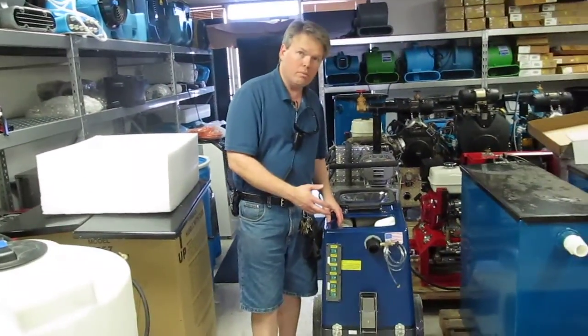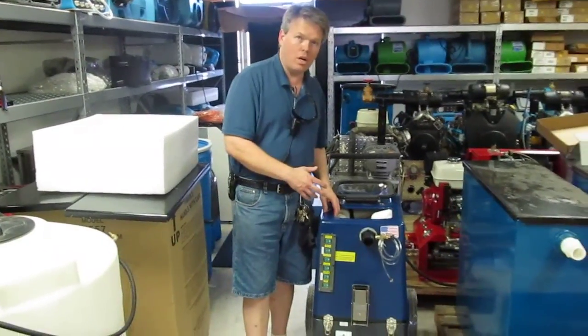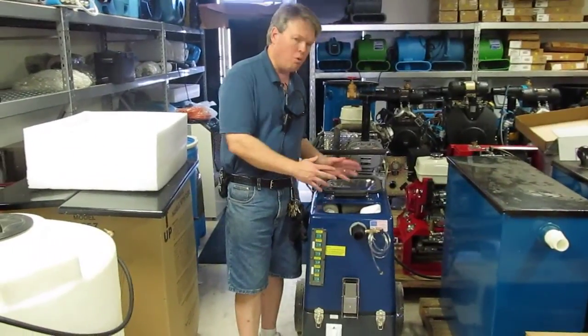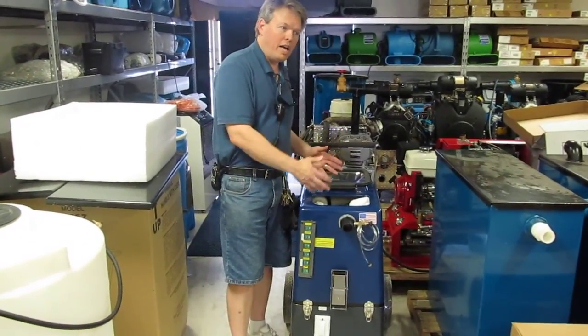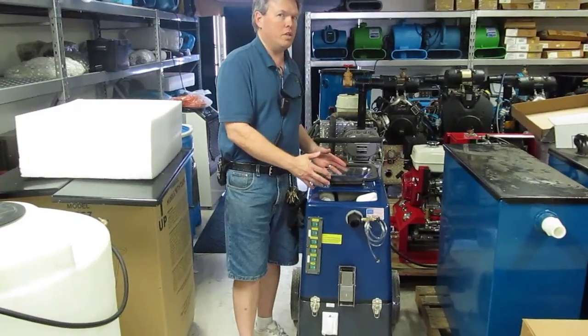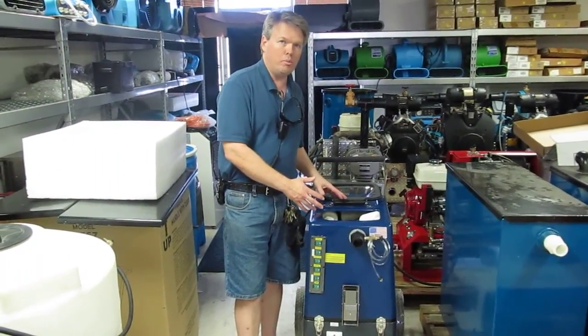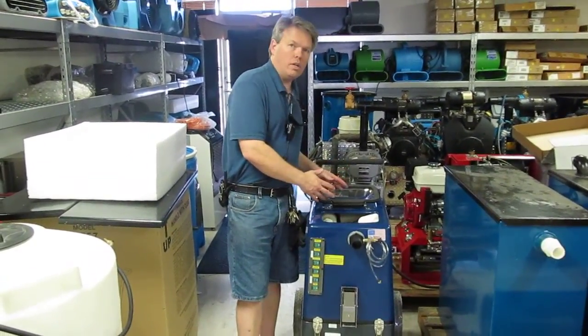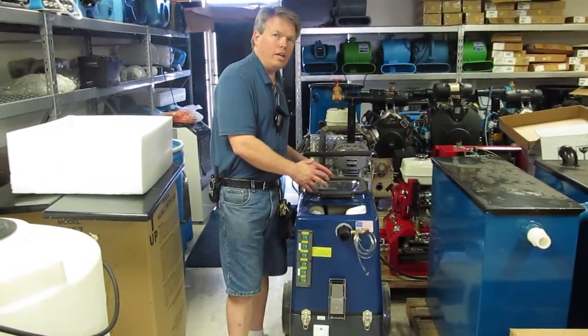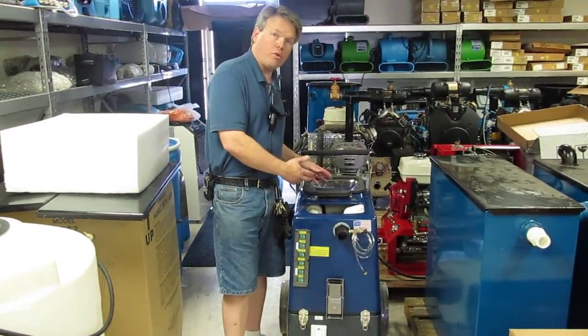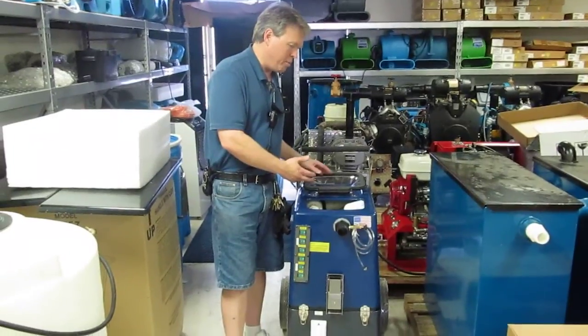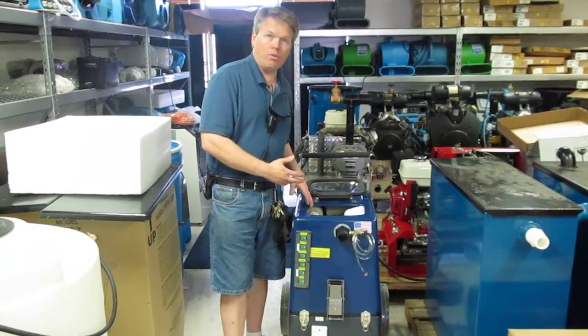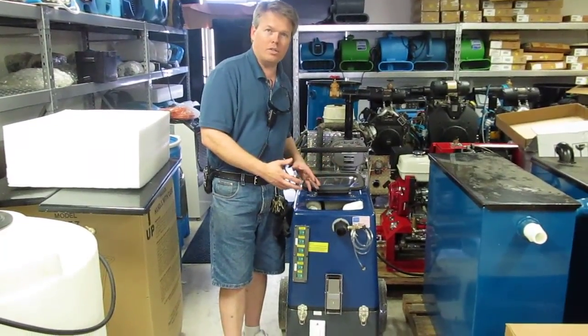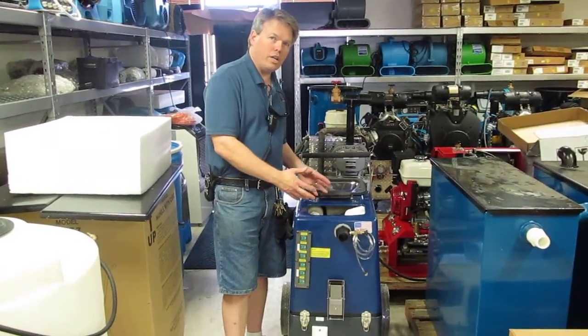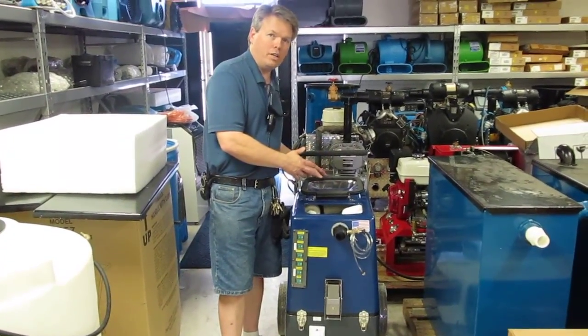Is that from the vac motor exhaust? Yeah, vacuum motor exhaust. So there are two options with the unit. You can have a heat exchanger, which won't use any electricity at all. We get up to a 30-degree temperature rise with that. We can also put a 1800 watt inline heater inside the housing, but it'll go to a third power cord if you go with that option. You can also do both and have a complete heat system where it'll preheat off the heat exchanger and then post-heat off the electric heater, and it's definitely going to be really hot.